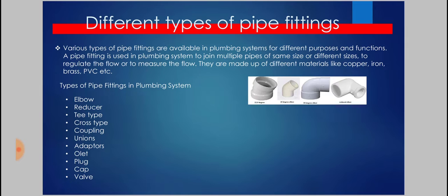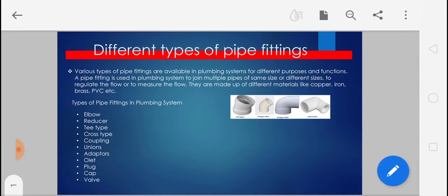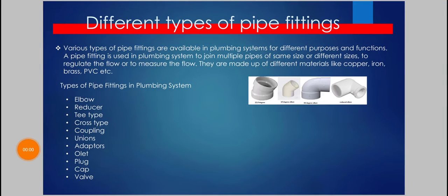The first type is the elbow. Elbows are used to change the direction of flow between two pipes. Elbows are generally available with an angle of 22.5 degrees, 45 degrees, and 90 degrees. If the pipes are of the same diameter then normal elbows are used; otherwise reducer elbows are used.